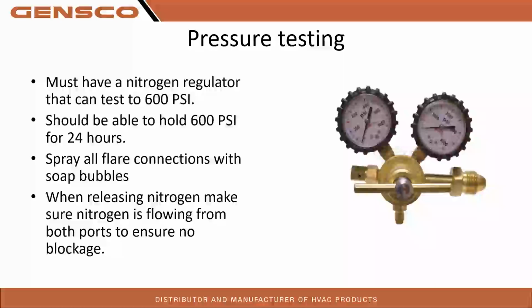When you guys are releasing your nitrogen from the system, or even before you start purging it, probably something I would recommend is purge nitrogen through your system, starting at your ports on the heat pump. Hook up to your suction side, pull your Schrader out of the liquid side, and just blow nitrogen through. Make sure you have flow through your branch box, through your heads, and then back out the other side of your heat pump there. I do get phone calls on new startups, restriction in the line, usually a kink, or somebody had forgot to take a cap off of their port when they hooked the line set up to it. Little silver discs come inside the fittings. Every once in a while, I will get a call and find that one of those things did get stuck in there. So, like I said, I definitely, before you seal your system up, pull a vacuum, all that, make sure that you actually do have flow through your line set. It's going to save you probably some headaches on that.